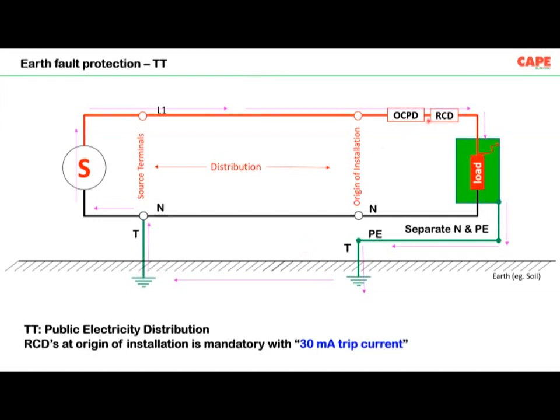I have shown RCD as a series device, but I'm sure every electrical engineer will know. This is just to show you there is a protective device. So in a TT network, for fault protection, a 30 milliampere RCD is mandatory as per this particular standard. Now, remember, this TT is only for public electricity distribution, not for industrial or commercial installation, or not for places where you have a transformer within your compound, or if you are an HT consumer, this is not applicable.